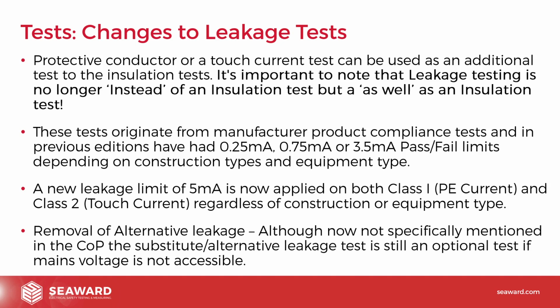It's still quite a powerful and useful test because it tests with AC. So it's an AC test, as opposed to the insulation resistance test, which is a DC test. There are faults and leakage that you will detect using AC that you wouldn't detect with DC. So we still feel it's a valuable test, and obviously we'll still include that on our products, but it's now not specifically or separately mentioned within the code of practice.